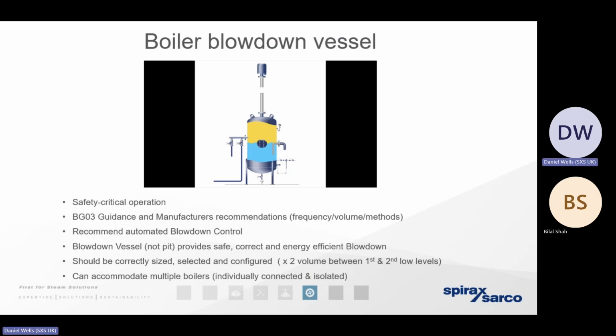But the main reason for that blowdown vessel is, if we've got hot water at 184 degrees coming out of that boiler, as it depressurizes, we're going to have that huge violent expansion. So it needs to be capable of allowing that steam to boil off and expand and be safely vented to the sky. Unfortunately, there's no opportunity for heat recovery here. The best we can do is to keep that blowdown to an absolute minimum.